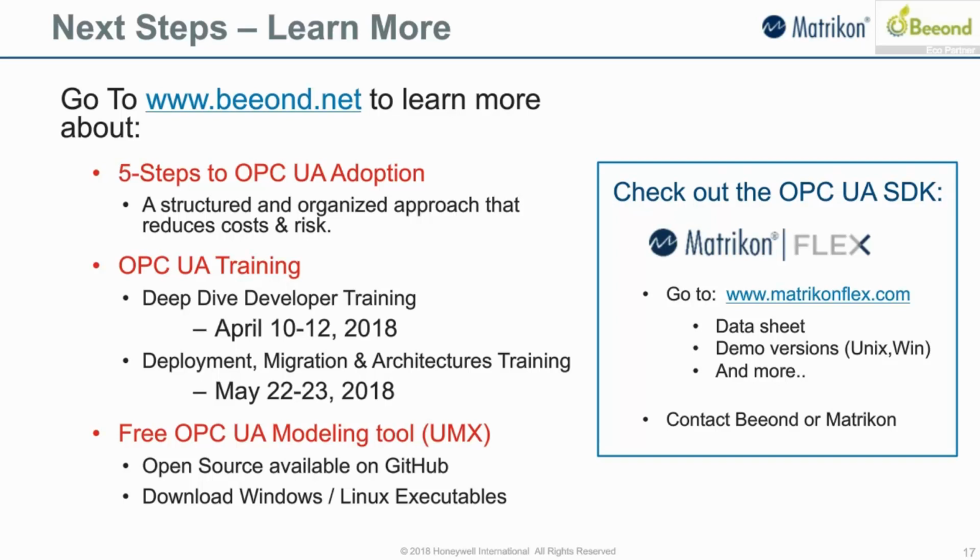So the OPC UA specification provides basically the boundary that it gets to is how to properly exchange messaging with other OPC UA components. And the underlying part is up to the programmers or the vendors of whoever's making the OPC UA server. They have to identify how natively am I going to talk to the underlying device? That's the part that's hidden from the rest of the world.